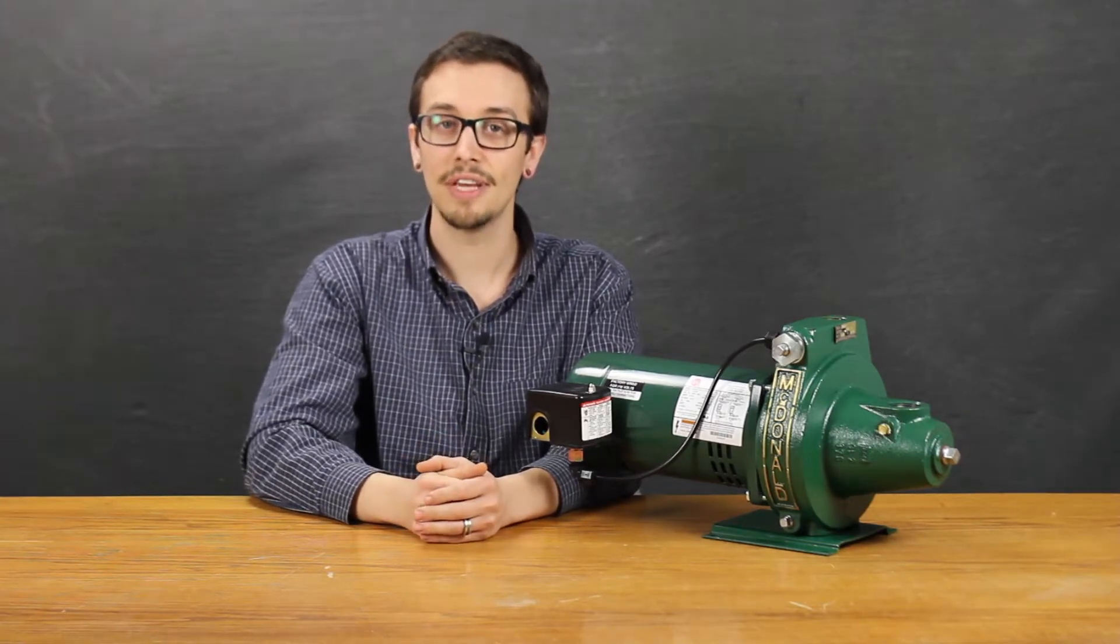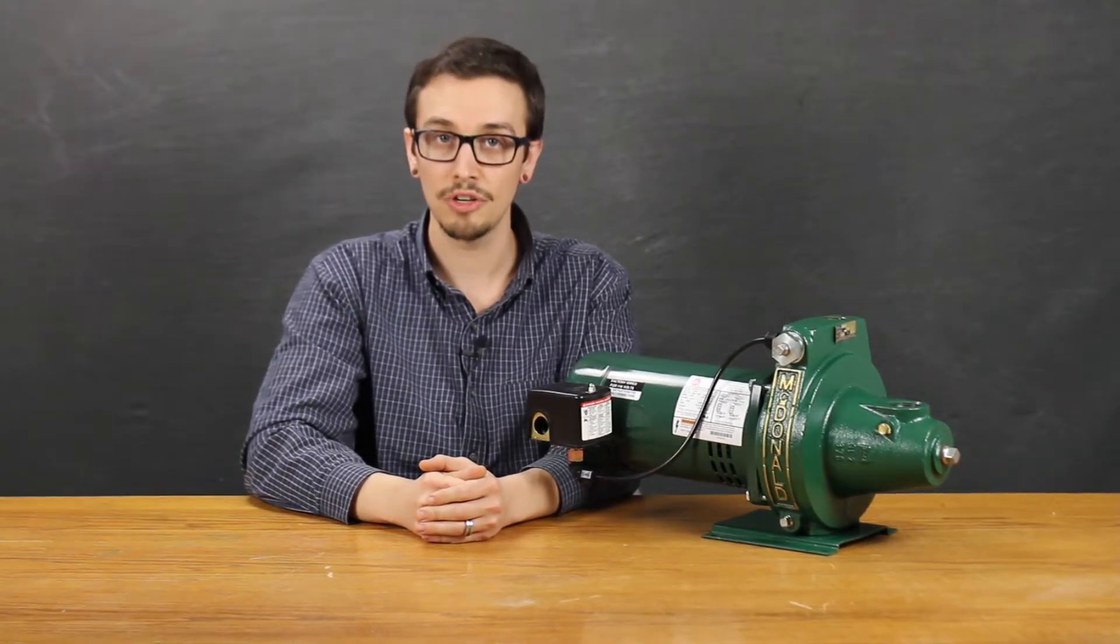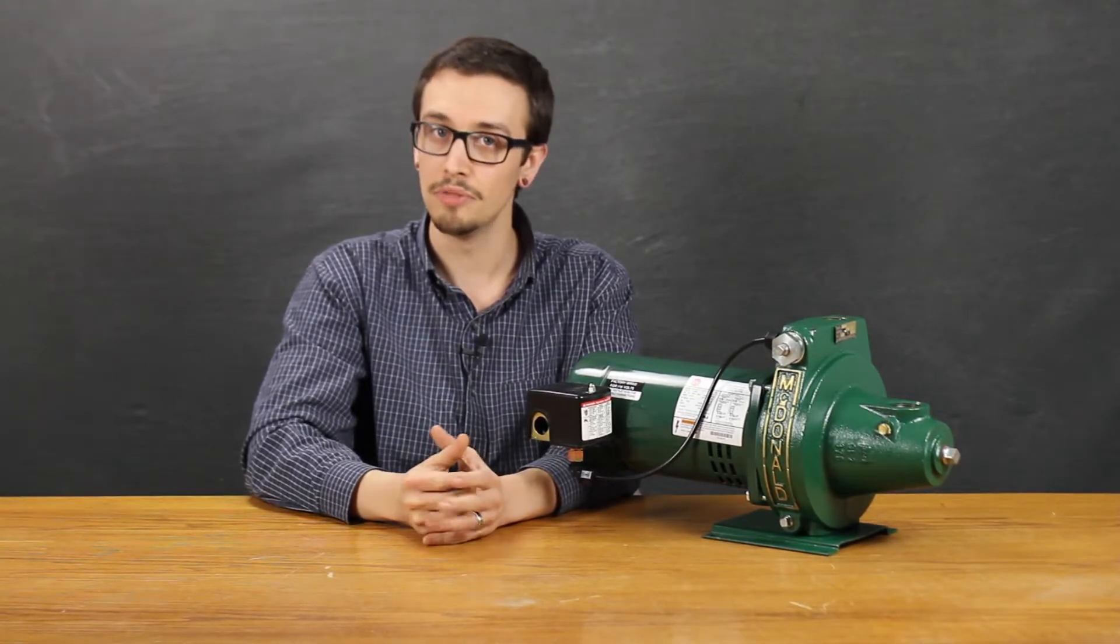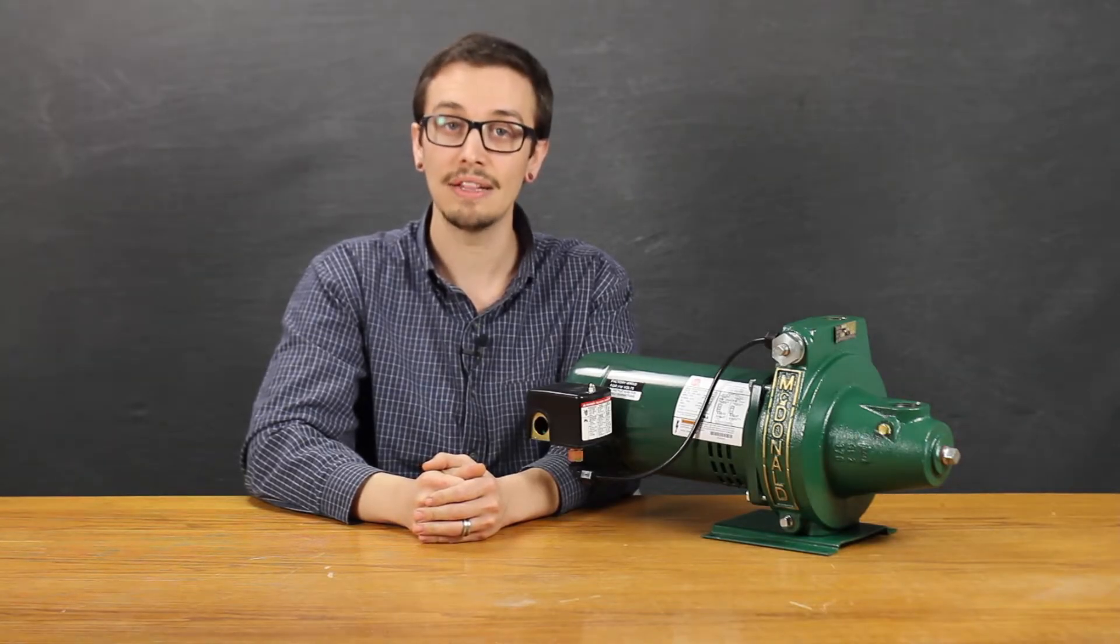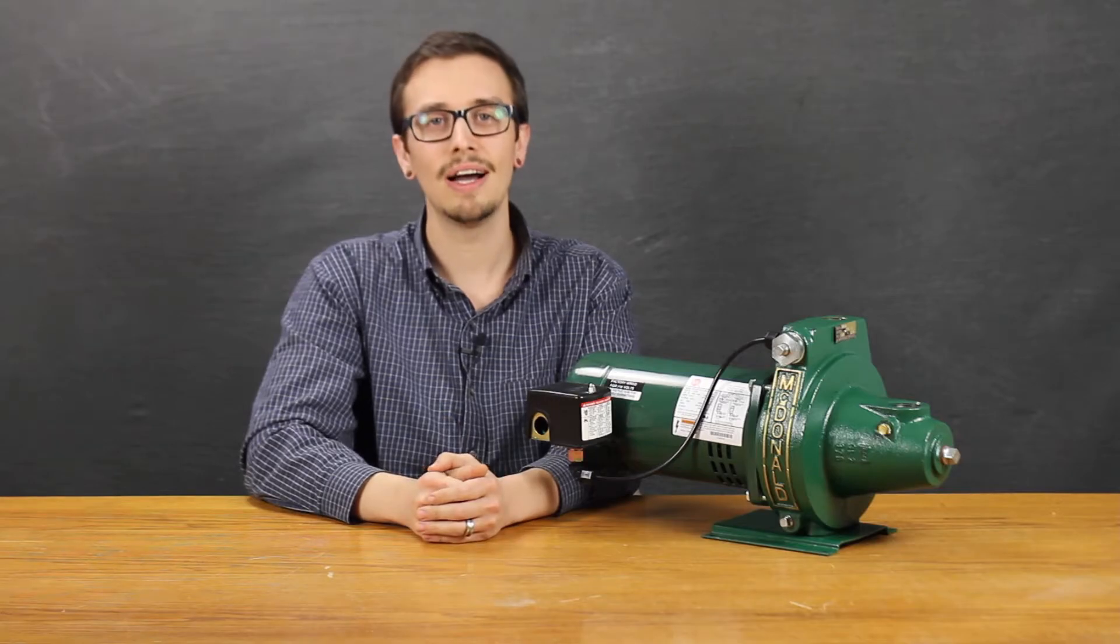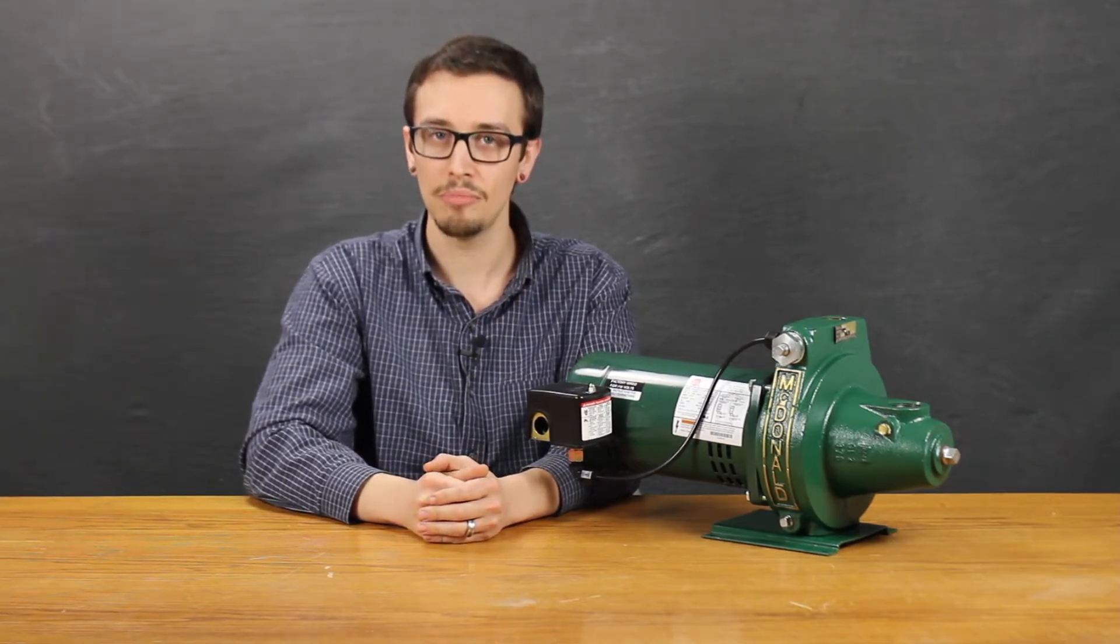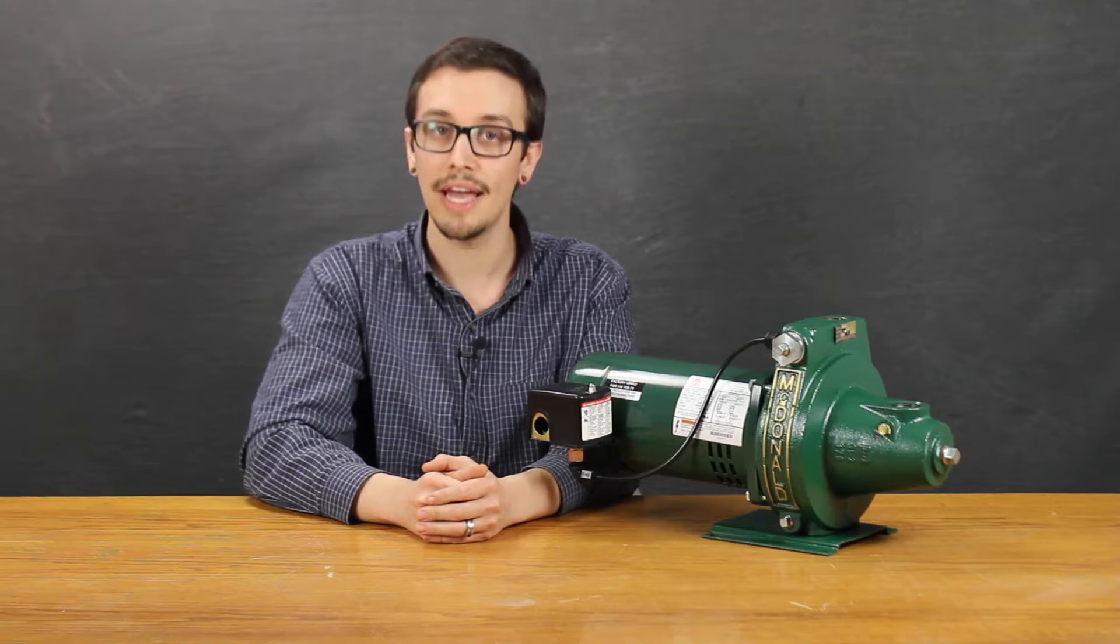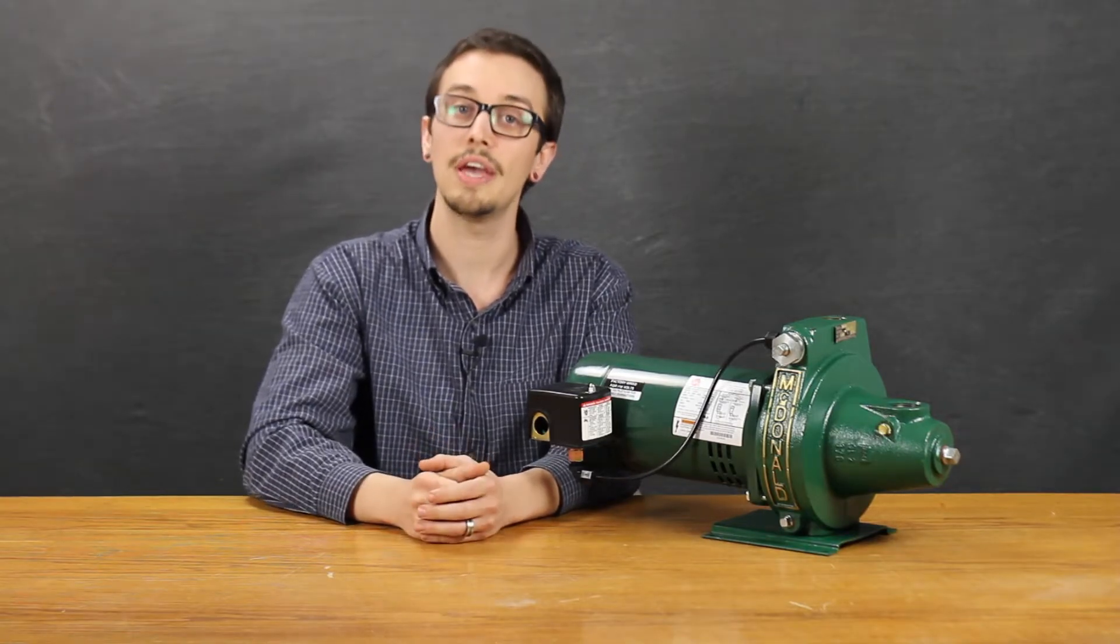The pump body has a certified lead free cast iron construction and motor mount. This means that the wetted surfaces contain less than one quarter of one percent lead. Because of the relatively high silicon content, cast iron has an inherent ability to resist scale and oxidation such as rust and corrosion.